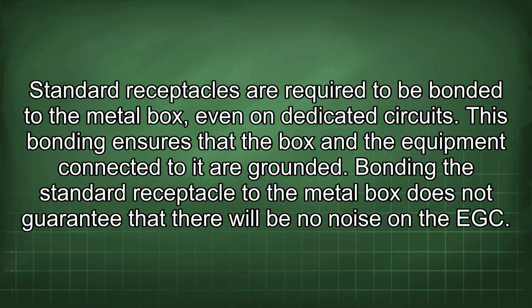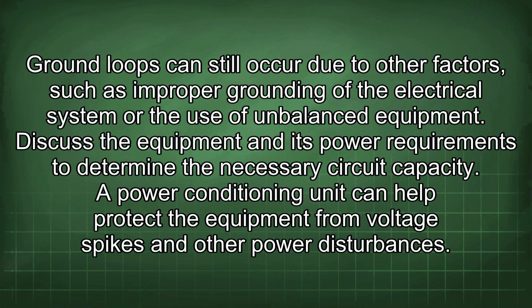Standard receptacles are required to be bonded to the metal box, even on dedicated circuits. This bonding ensures that the box and the equipment connected to it are grounded. Bonding the standard receptacle to the metal box does not guarantee that there will be no noise in the EGC. Ground loops can still occur due to other factors, such as improper grounding of the electrical system or the use of unbalanced equipment. Discuss the equipment and its power requirements to determine a necessary circuit capacity.